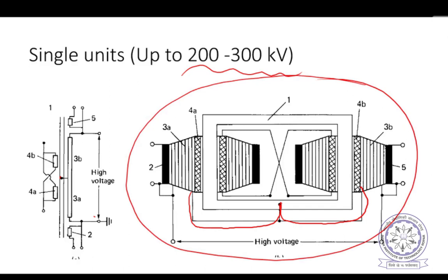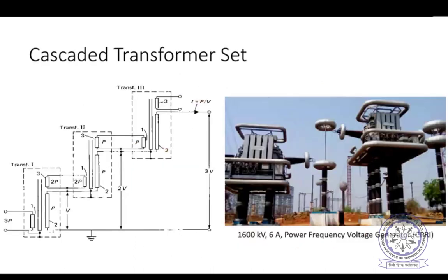But as I have pointed out, in the case of DC we need multiplying circuits, because 300 kilovolts is not at all sufficient to test power equipment insulation. For extra high voltage, we need thousands of kilovolts, even megavolts generation. For such voltage generation, we do need multiplying circuits. So this is how the cascaded transformer set works.